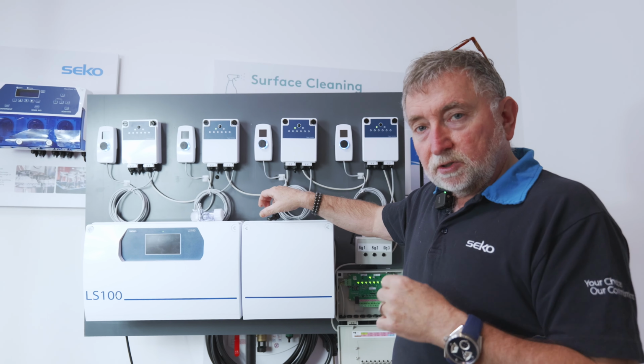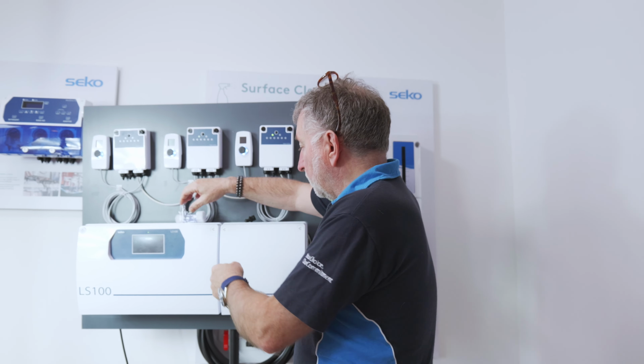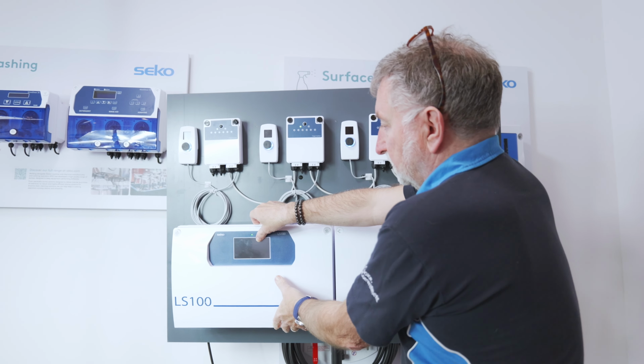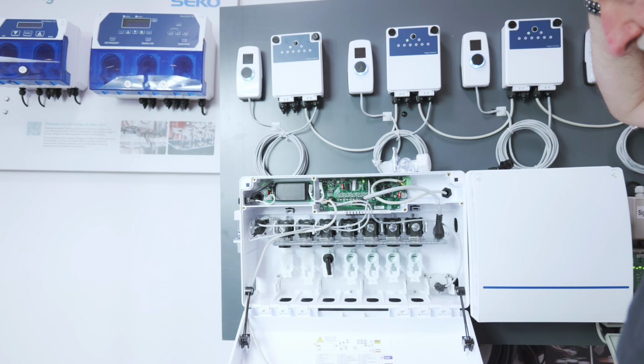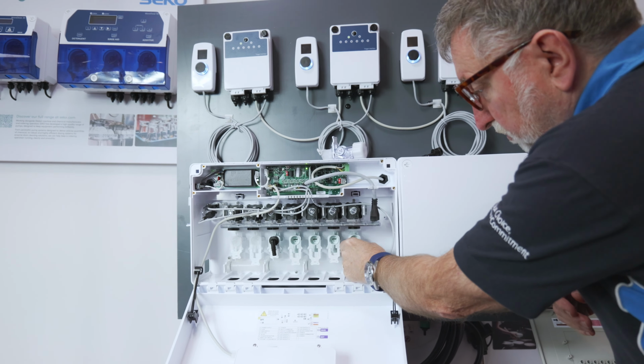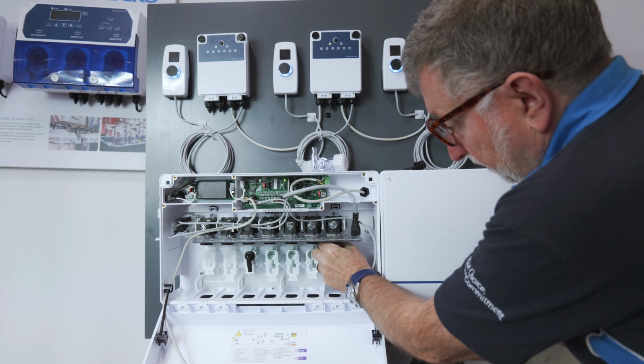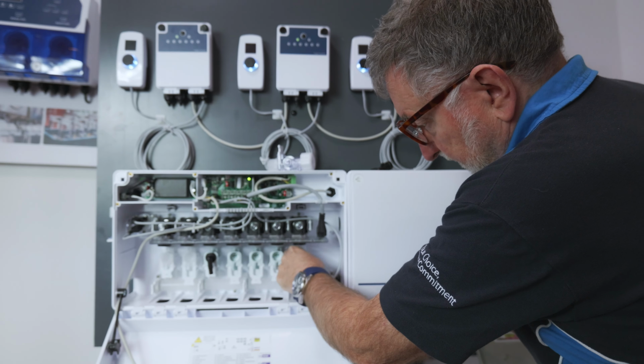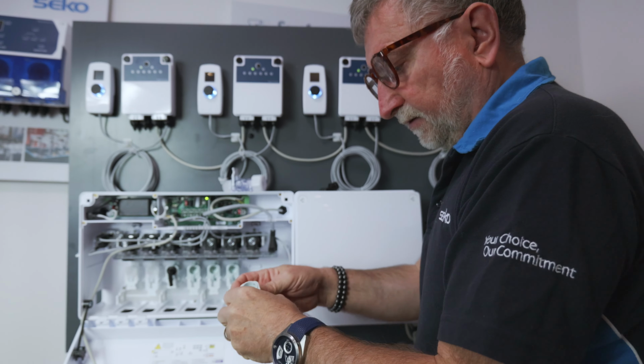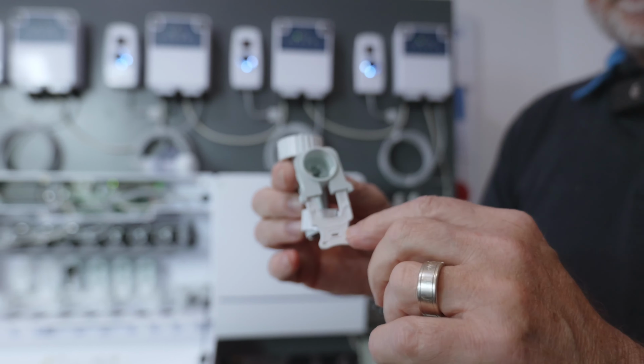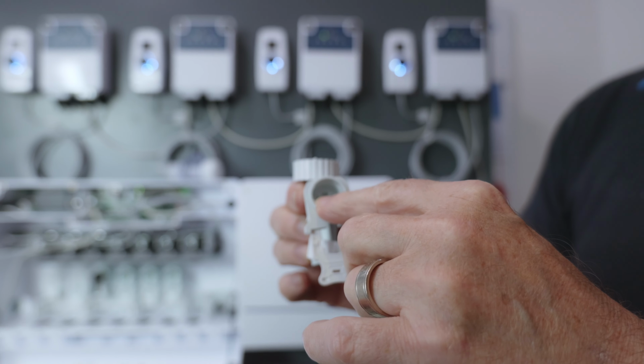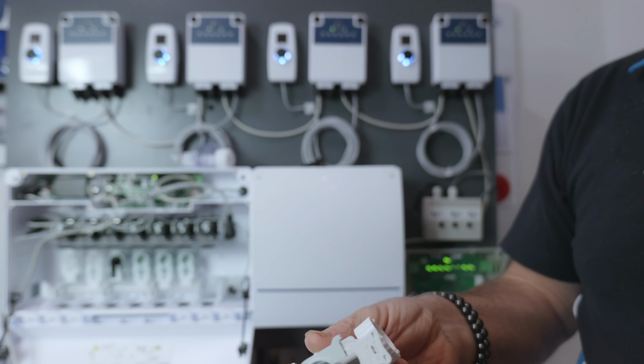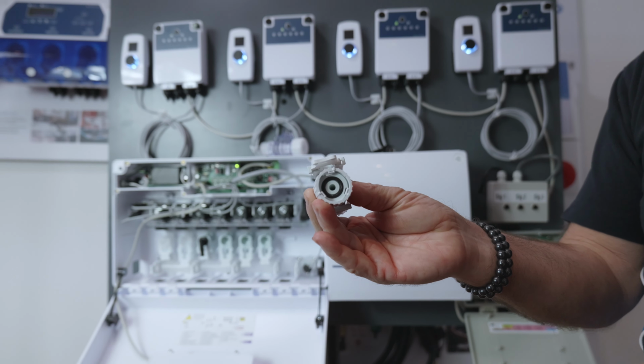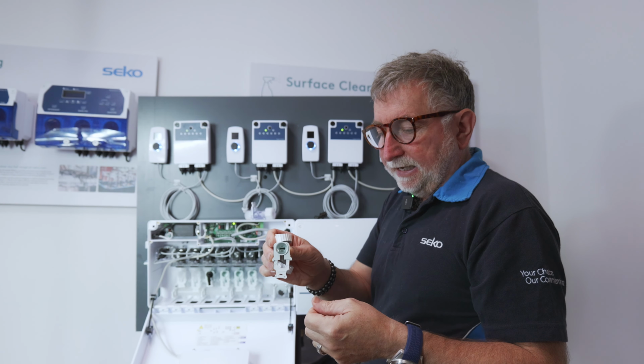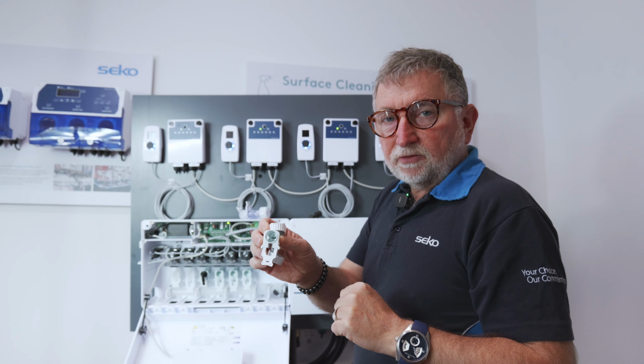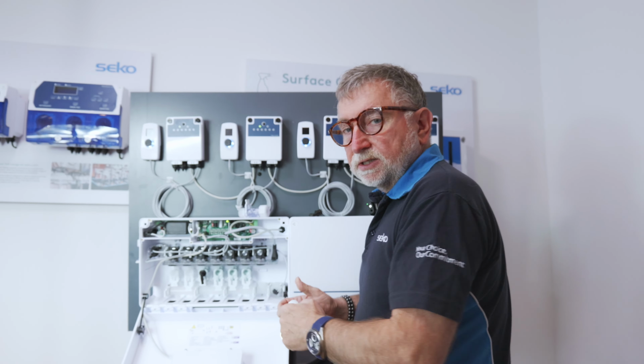The only other part to check if you do have a low chemical flow would be one of the check valves. Now in here they're fixed with quarter turn fittings, which can be rotated and the check valve removed. We can see in there the Venturi inlet, which can become blocked if you have a product which is prone to clogging or becomes quite viscous and sticky. Just simply flush these again through with some hot water, and then you can replace in the system in the same way.